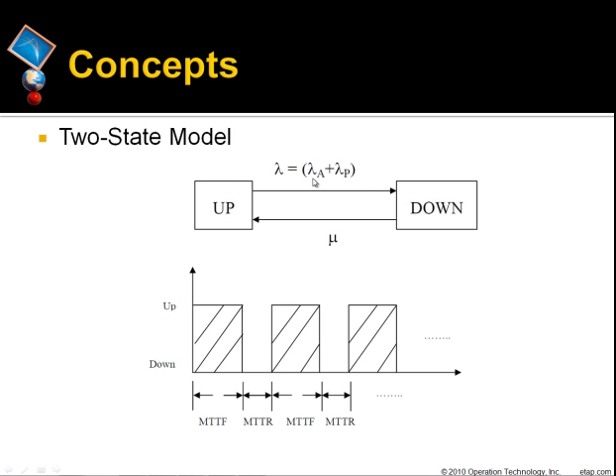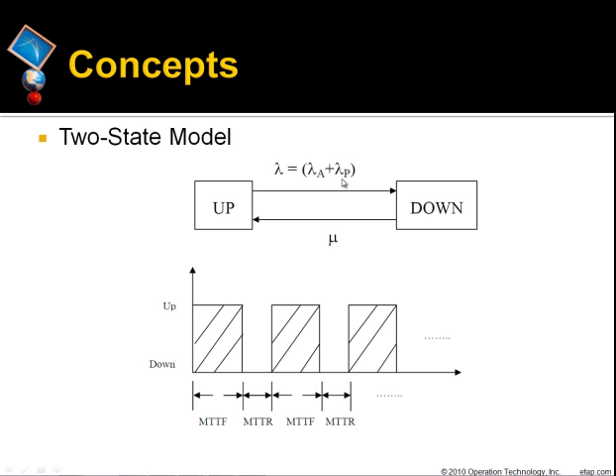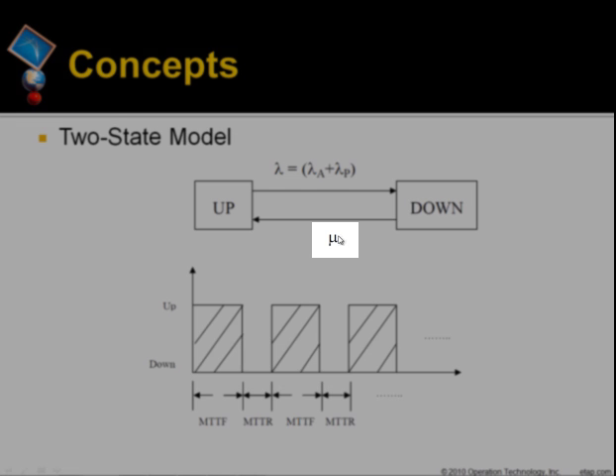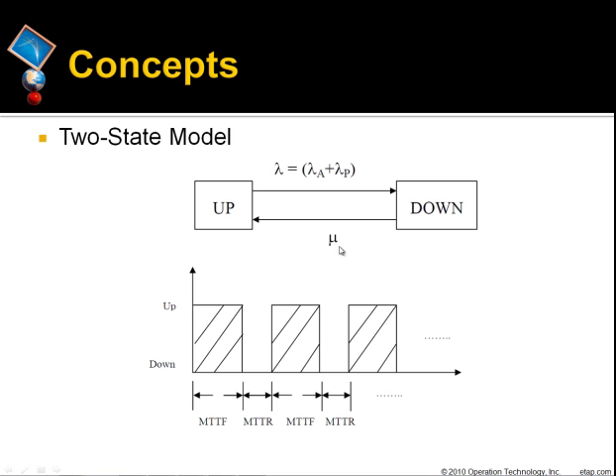An example of active failure would be a short circuit fault. Passive failure rate, number of failures per year, represented by lambda P, does not cause the operation of protection devices and therefore does not have an impact on the remaining healthy components — for example, an open circuit fault. Mean time to repair in hours, or MTTR, is the time it takes to repair a component outage and/or restore the system to its normal operating state. Mean repair rate, number of repairs per year, represented by mu, is equal to 8,760 divided by the mean time to repair.